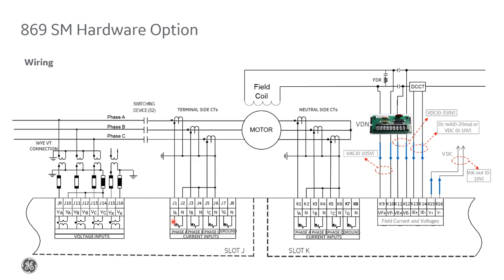Again, just to give you an idea of the wiring to the relay, these left three terminal blocks, the two in slot J and the first in slot K, these were existing input options for your standard VT and line CT connection, and then your differential CTs on the neutral side. What we've added with the synchronous motor option is this input block here on the right, where we have inputs for your field winding voltage taken across the discharge resistor, and your exciter voltage, again, routed through this voltage divider network that steps down the signals to relay processing level. Then we have the input for the DC-CT, and again, the output for power factor regulation.